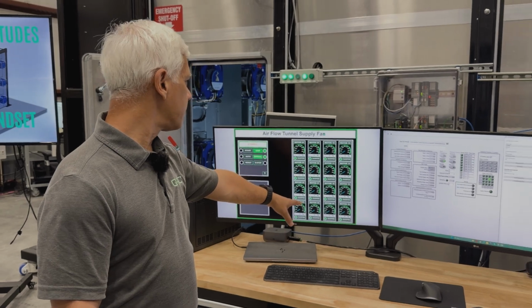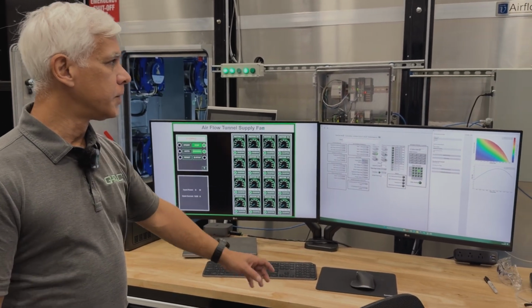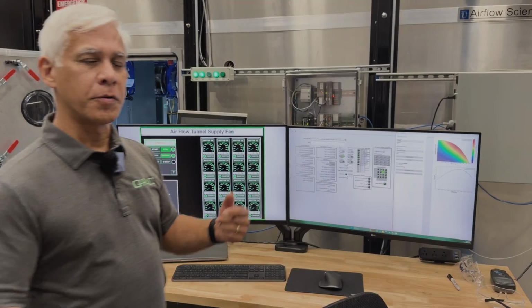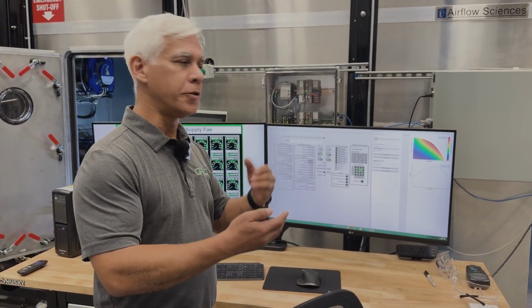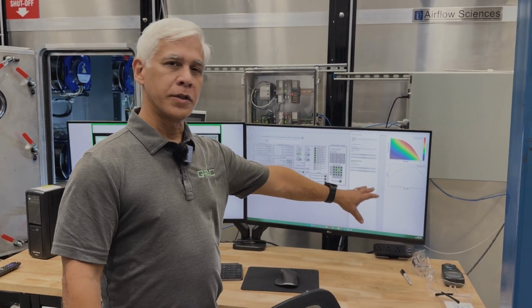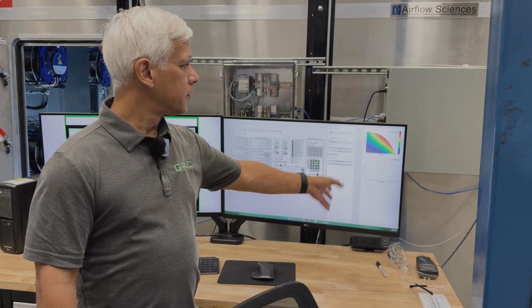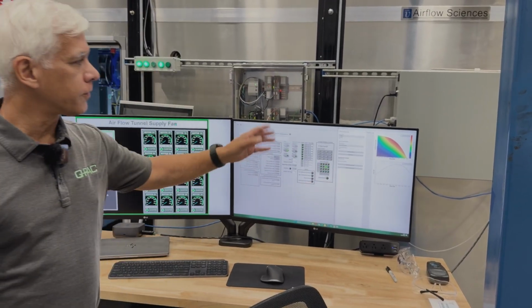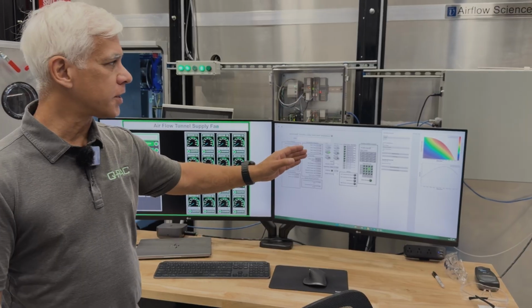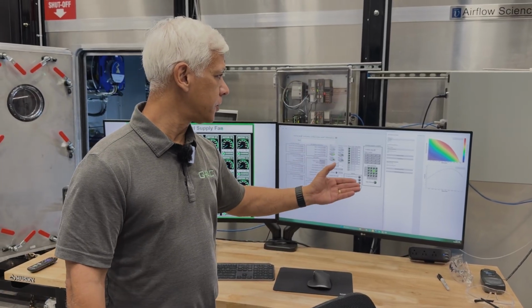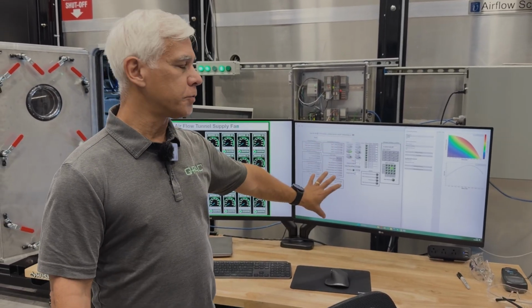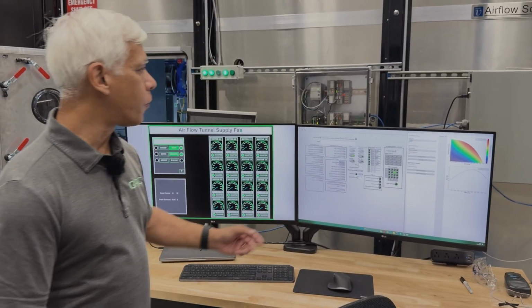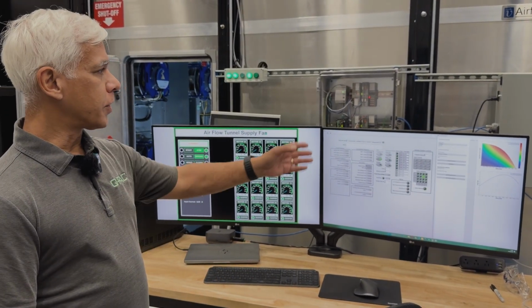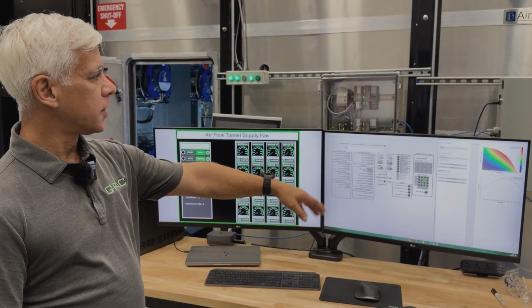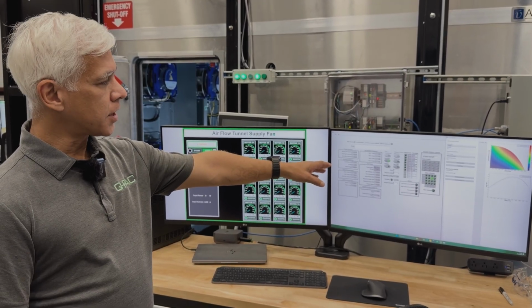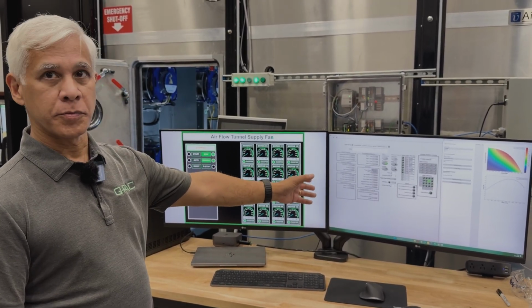And we have 14 fans for that, and a way to control those. We were just talking a little bit about pressure and airflow and the duty point. So we have some software here that lets us model that, predict that. For different fan models, we can put in whatever size fan array we want to test. And then this is the actual software in its current state for running the test. We can control how many nozzles are open and closed. We can set our set point for CFM, and we can monitor the pressure.